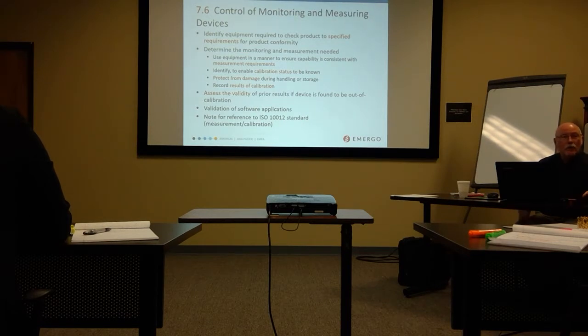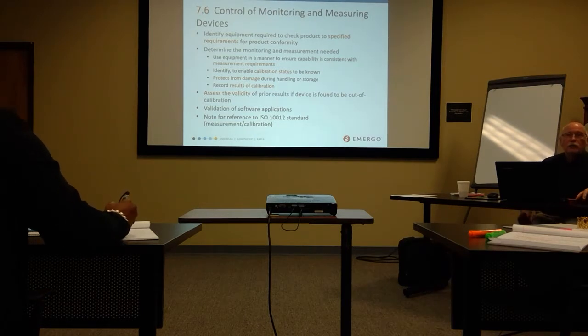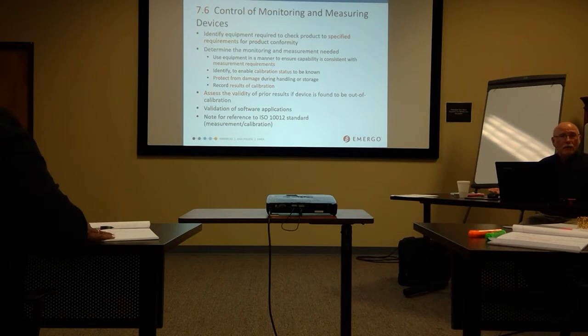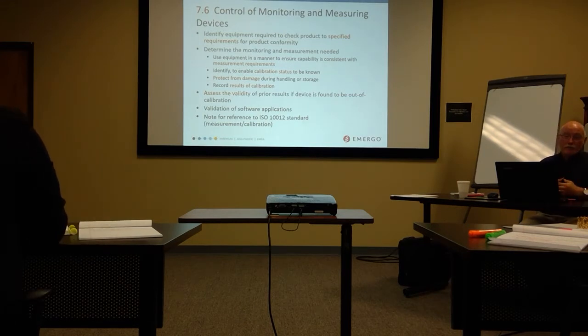So this calibration process is critically important. If you get a result back that says out of calibration, your procedure should have very explicit directions on what to do. You run screaming to QA, say, what do we do now? So investigation, what's the possible impact of this thing being out of calibration? It may be no big deal. It could be a very big deal. Many of these instruments are calibrated on an annual basis. If it's found to be out of calibration, what do you know? Do you have any idea when it went out? None. The only thing you know is that at the last calibration it was in date, and sometime between that date and now, it's out.